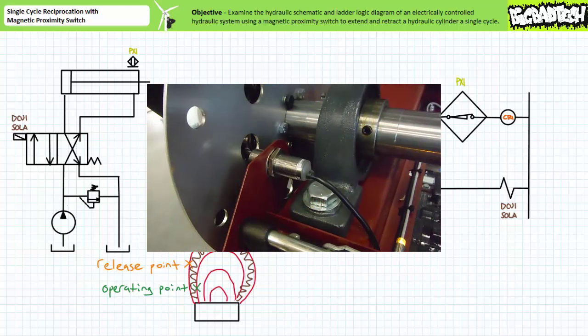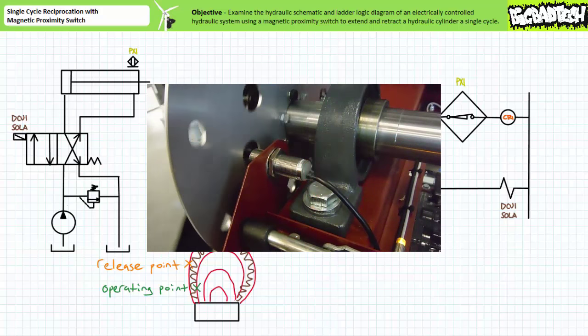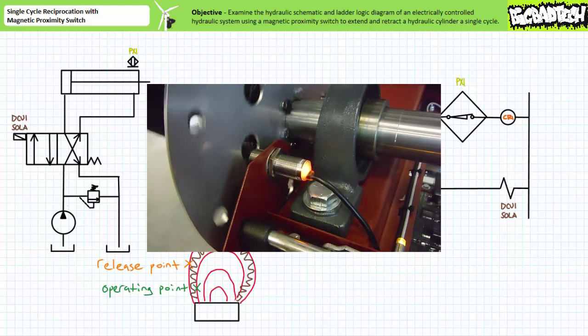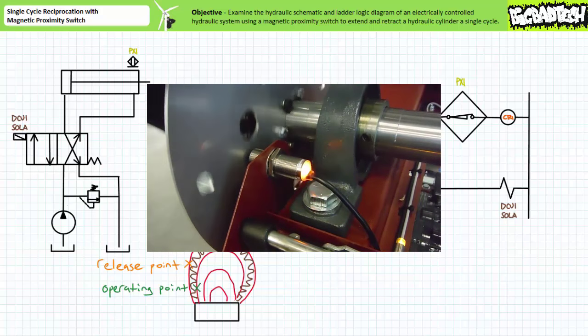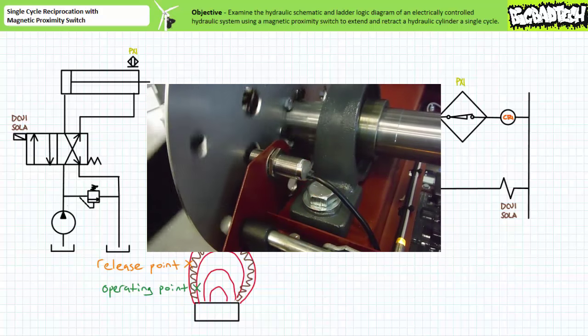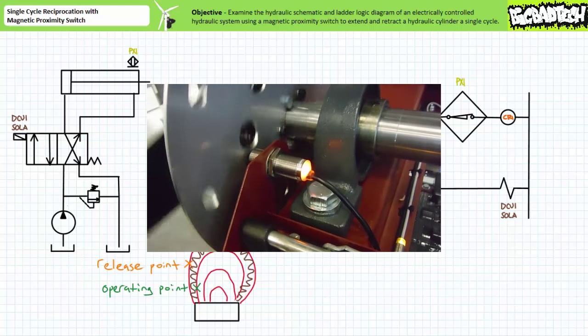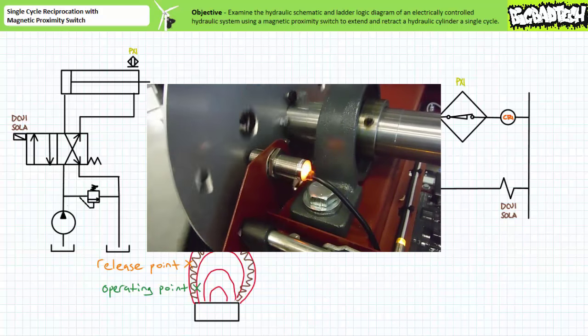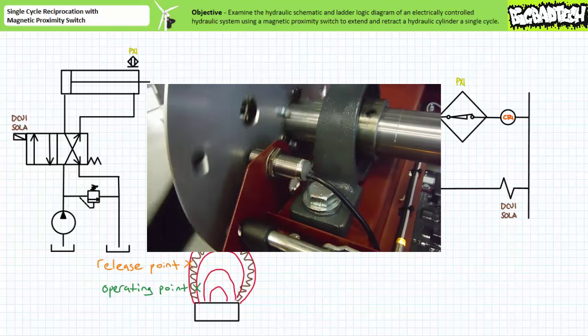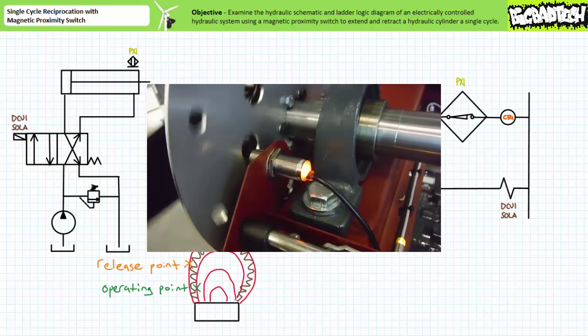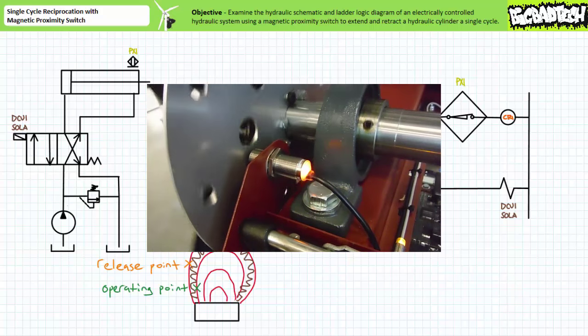Additionally magnetic proximity switches serve as essential components in some types of non-contact tachometers. Due to the non-contact nature of the magnetic proximity switch the rotational speed of a shaft can be accurately determined without unduly influencing it. For example a pulsar is a type of non-contact tachometer that detects the presence or absence of a magnetic tag on a shaft. Every time the tag passes the switch it changes states, and with additional circuitry like a counter and timer the rotational speed can be calculated. If a pulsar detected 30 transitions per second using a single tag, the shaft speed is 30 revolutions per second or 1800 rpm.